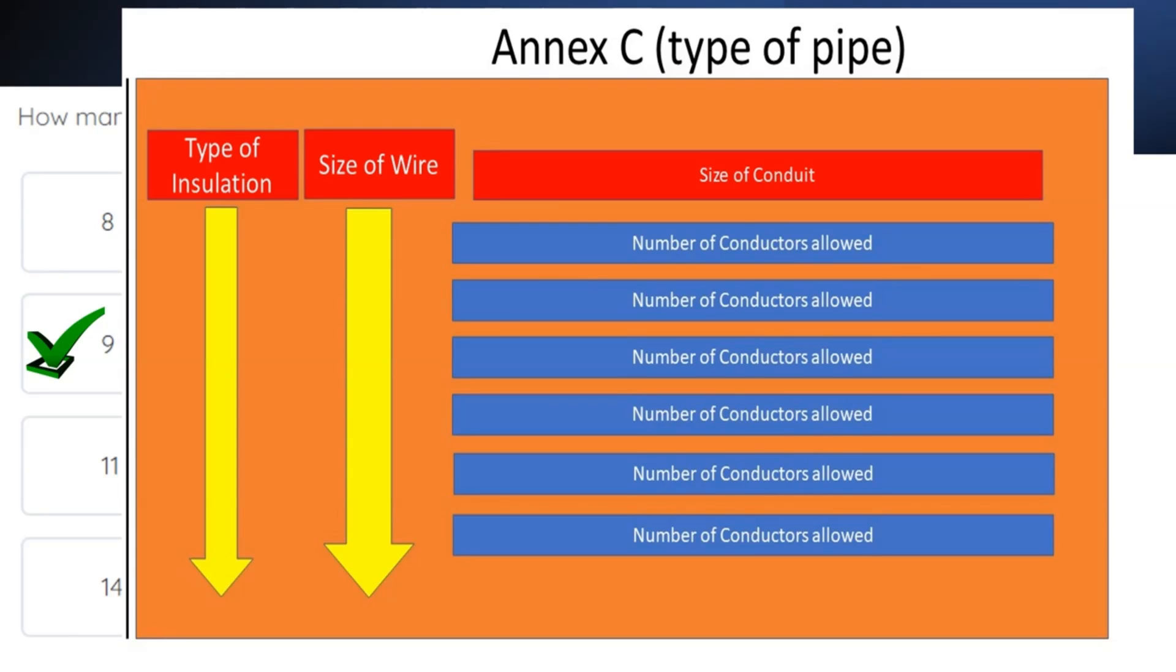When we verify that we're in the right table, we're going to start on the left-hand side until we find our installation type. Then, when we find it, we're going to come over and make sure that our wire size is listed. Then, we're going to come over and find our size of conduit, come down and tee off, and find the number of conductors allowed.